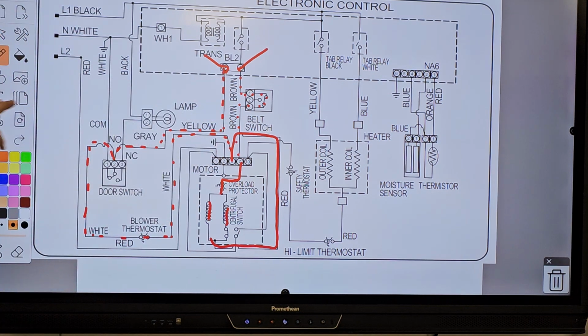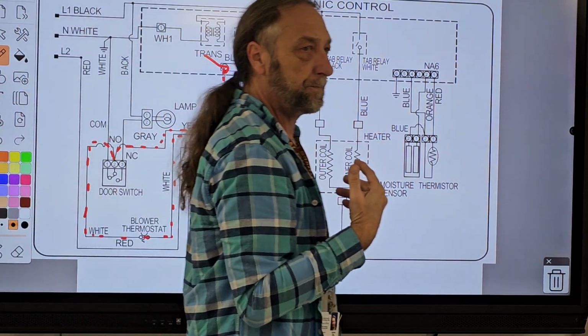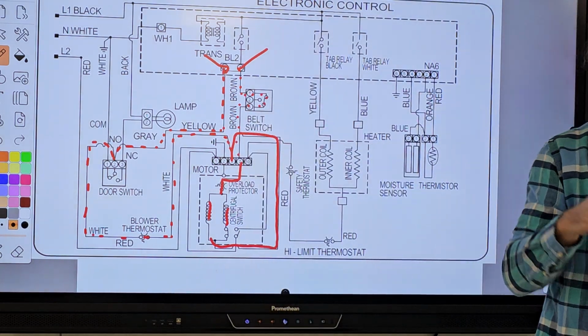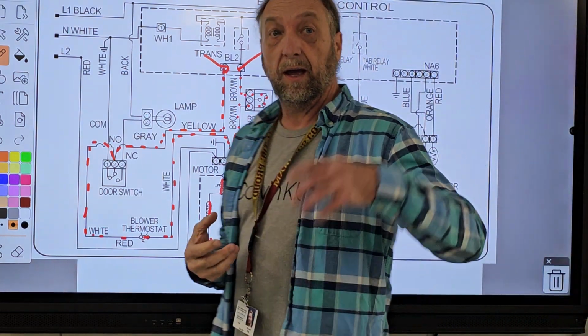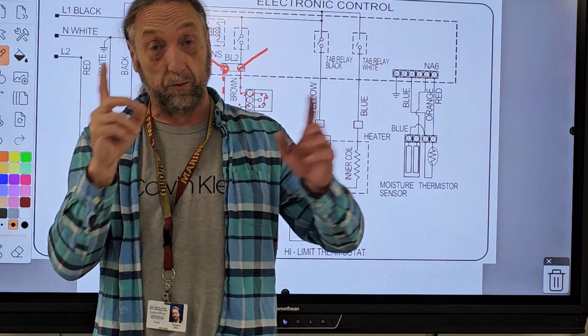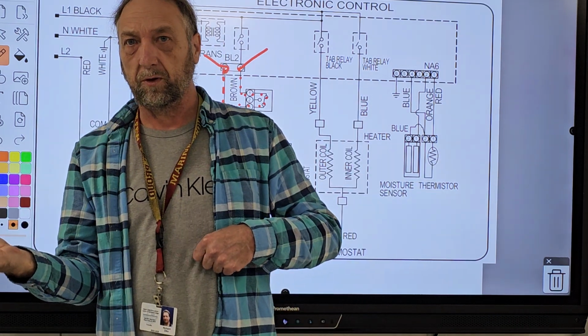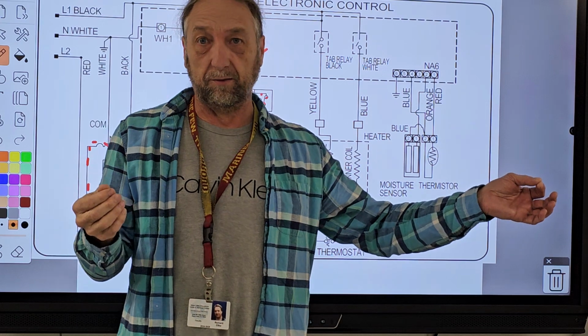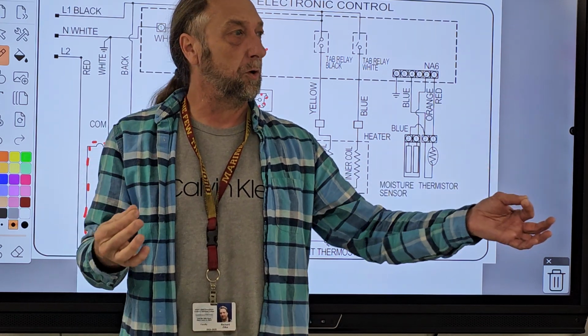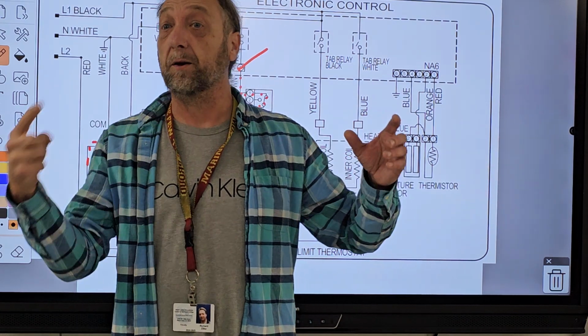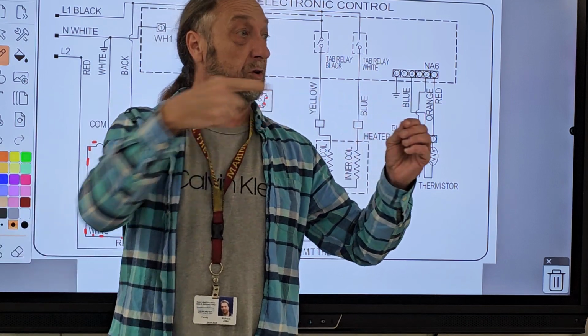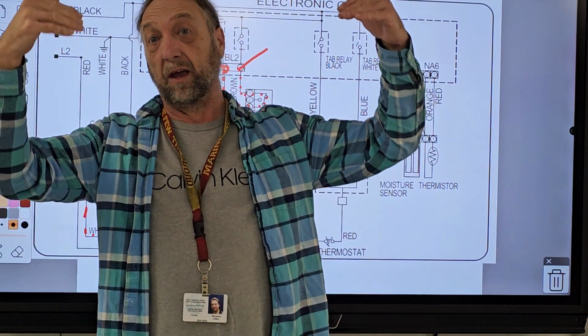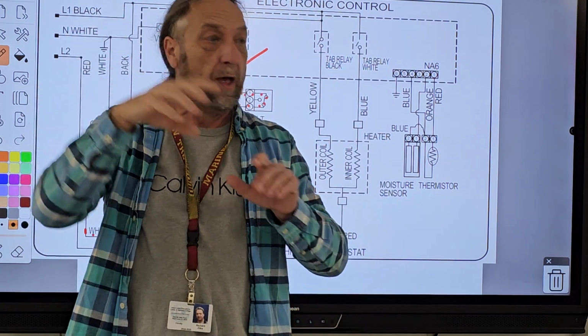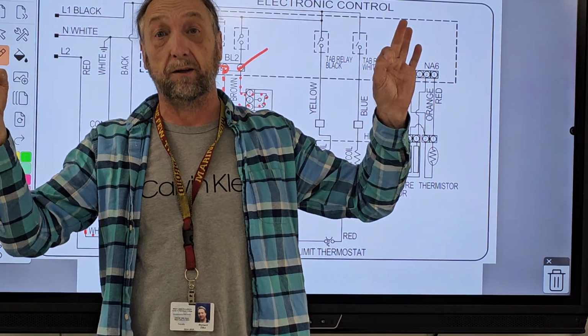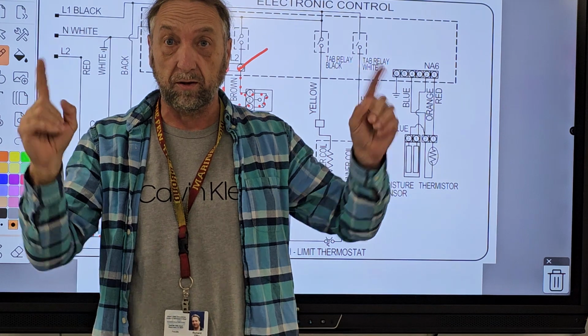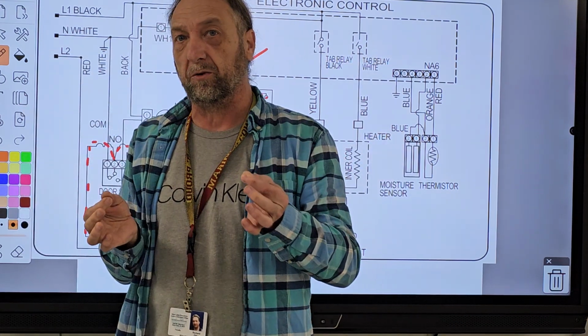So what test am I making there? What am I doing right now? A continuity test. We talked yesterday, me and Coyer, about continuity versus ohms. A wire has continuity but 0 ohms of resistance. The winding in a motor has continuity, but actually has a resistance value of 3 or 5 ohms. Continuity just means it's not broken inside — it doesn't mean the part's good. Actual resistance values tell you if the part's good or not.